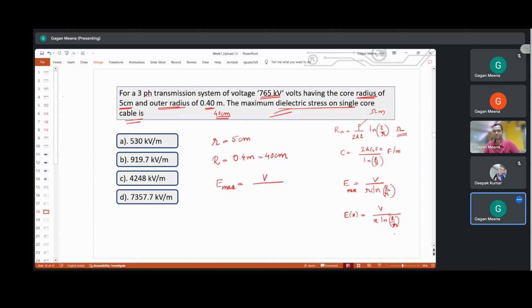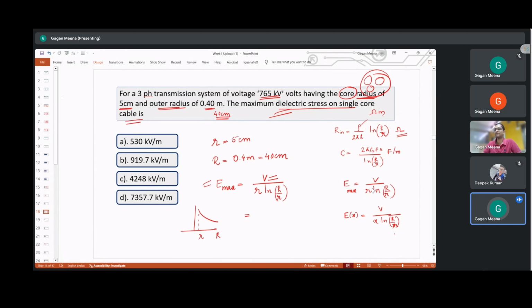Now one thing we have to remember is that this voltage is per phase, for each core. In a 3-phase cable we have 3 cores in 1 cable, so this voltage has to be phase voltage. Whenever a 3-phase system is given and nothing is mentioned, it is always the line-to-line voltage, so we want phase voltage, and we will divide it by root 3.